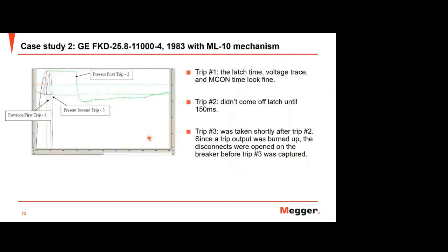Okay, and then this one is another case from some document. I will make it fast. You can see this is the latch time. Trip 2 is higher, 150 milliseconds. So after investigation, this is short after trip 2. This way we can detect some problem on the coil current, the coil part.